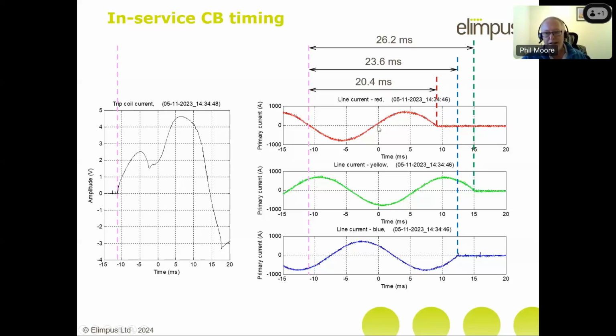I've shown this with line current, and if I'd had time, I'd have changed it to a slide that showed you the terminal voltage going from the 50 Hertz to the reactor transient, because it occurs at exactly the same point. But you can measure the time from the circuit breaker being told to operate to the current going out, and you can see that allows you to do it. And that's an in-service measurement. That's not an offline test. That's actually being measured as the device is operating.